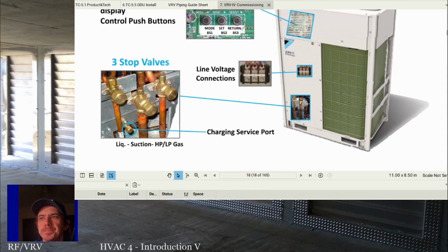So they would have an oil equalization line that went to all 3 outdoor units, so that if there was a lot of oil in one compressor but the other one was running low, the oil would equalize through the line basically. But I guess the design of these things has come to the point such that they don't need that fourth line anymore. So most of your modern ones, and I say modern, most of your ones made in the last 5 to 8 years, don't have that extra line, whereas the older systems did.